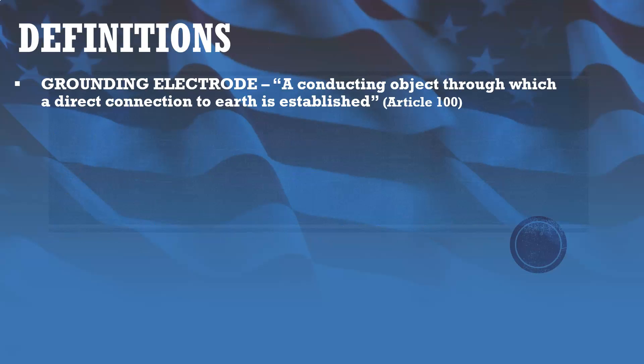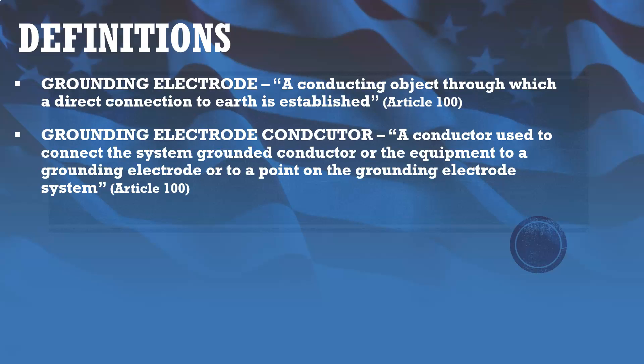Definitions. A grounding electrode is a conducting object through which a direct connection to Earth is established. Our definition of Earth is just the Earth — dirt. So essentially, a grounding electrode is some object we use to connect to the Earth with. A grounding electrode conductor is a conductor used to connect the system grounded conductor or the equipment to a grounding electrode or to a point on the grounding electrode system. In other words, it's a conductor that we use to connect something to a grounding electrode with.